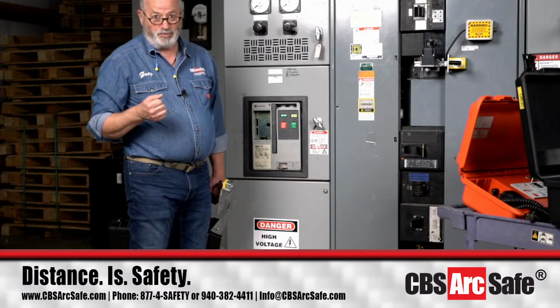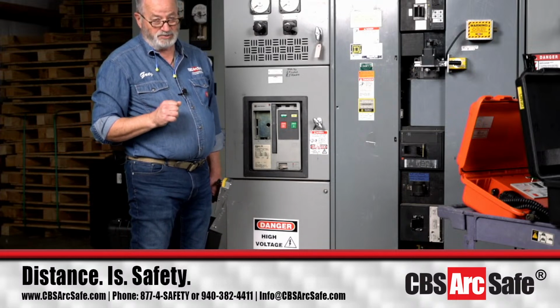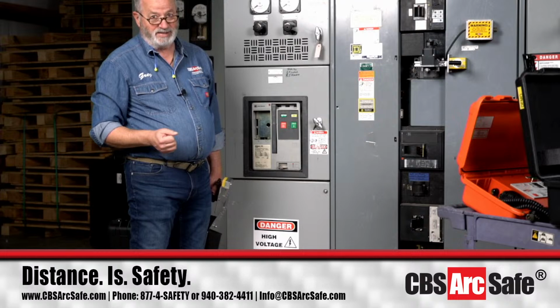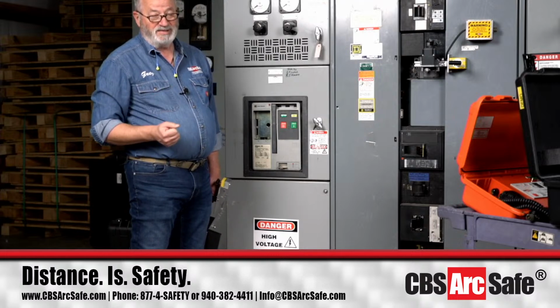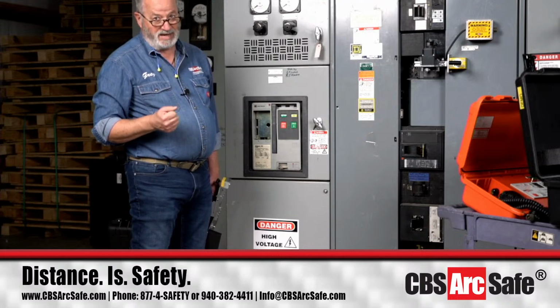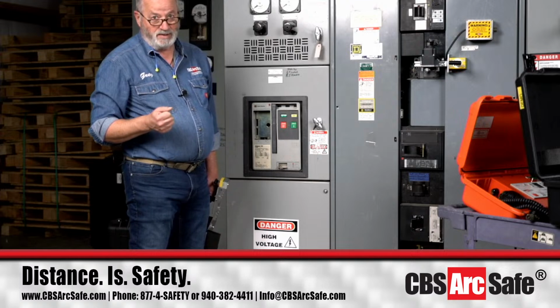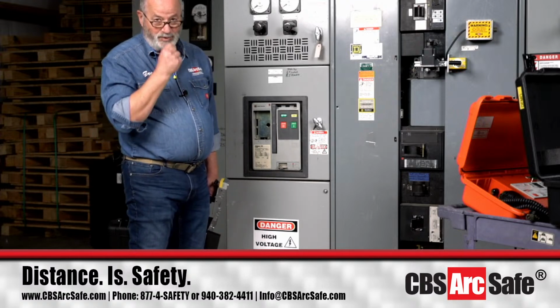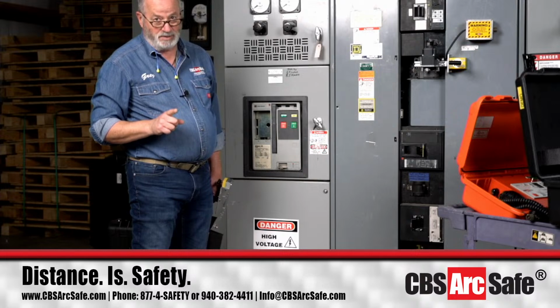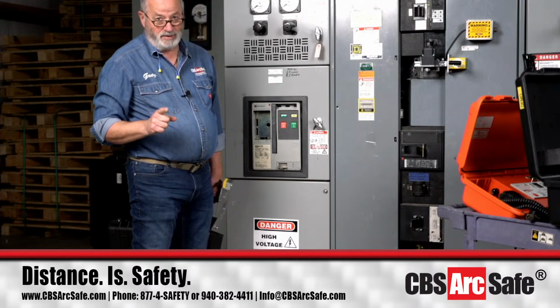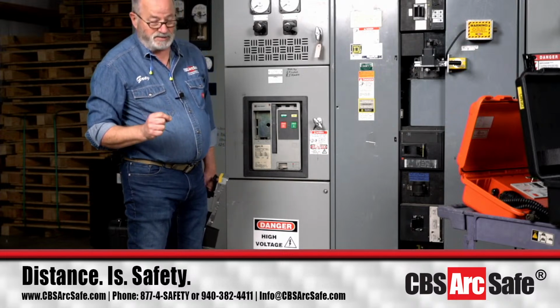And I simply have to tell people, the breaker is not supposed to close on its own when you get to the bottom of that last stroke. If you have something like that happen, the breaker is trying to tell you you need maintenance. Okay? So just understand, remote racking and remote switching don't fix a maintenance issue. They can help you identify one, but you've got to get it fixed. That's the bottom line.